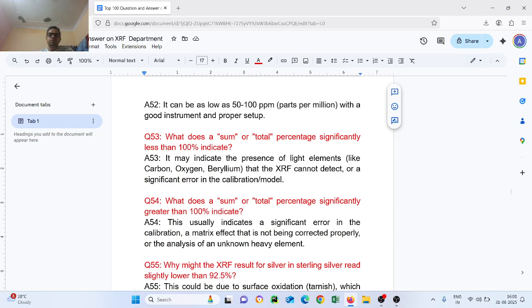Question number 53. What does a sum or total percentage significantly less than 100% indicate? It may indicate the presence of light elements like carbon, oxygen, beryllium that the XRF cannot detect, or a significant error in the calibration model. Question number 54. What does a sum or total percentage significantly greater than 100% indicate? This usually indicates a significant error in the calibration, a matrix effect that is not being corrected properly, or the analysis of unknown heavy metals.